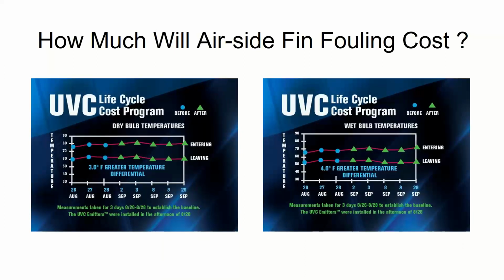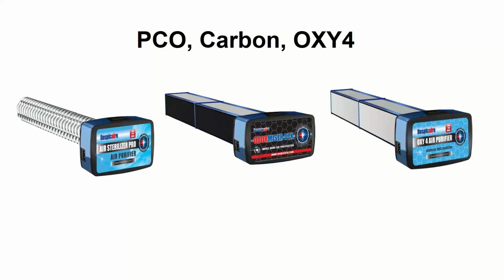Coil temperatures, this is showing an average of 3-degree improvement on coil temperature, meaning instead of providing 58-degree cooling air, you can go back to providing 55-degree cooling air, which means I need less CFM, less airflow to get the job done. Similar thing on the wet bulb side.